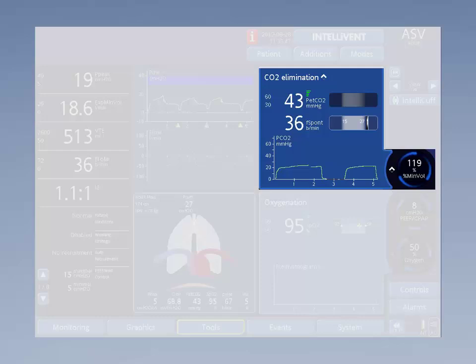If the level of spontaneous breathing decreases, IntelliVent ASV will further promote spontaneous breathing by decreasing the minute volume slowly to achieve a higher ETCO2. If the spontaneous activity continues to decrease, the built-in safety measure of the ETCO2 controller takes over.